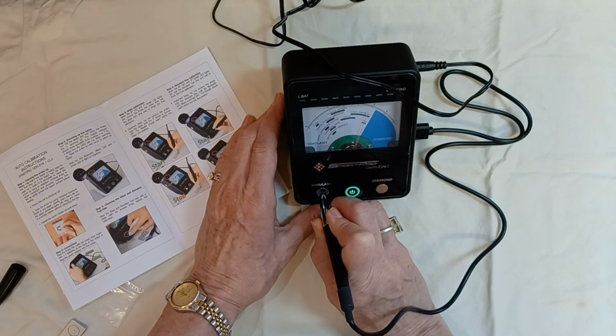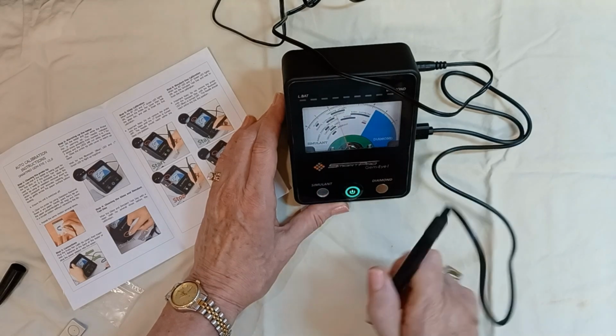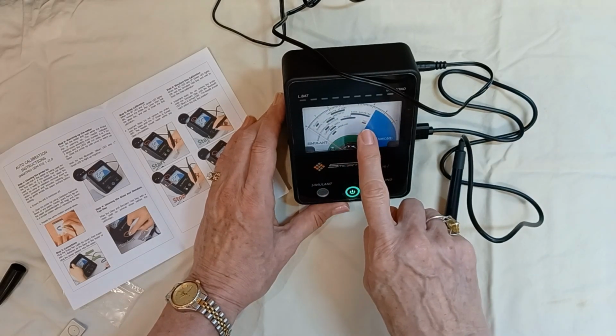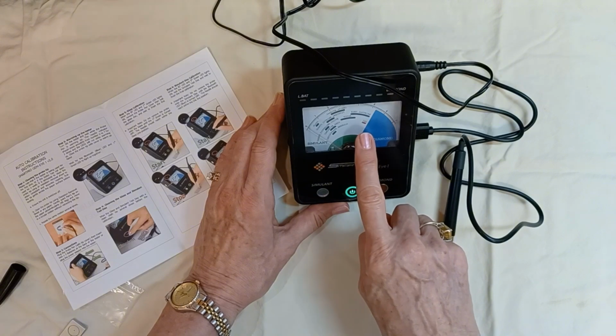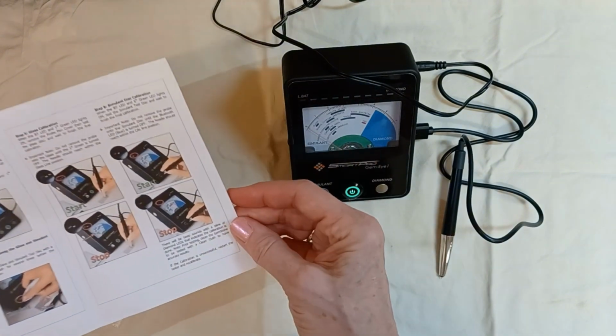Do not remove it until the blue LED is off, and it should be within cal, which it is right there. The little red dot that it's going through, that's the calibration dot. I should have zoomed in a little bit on that, but right here's the calibration dot, and that's where the needle was. So it is calibrated.